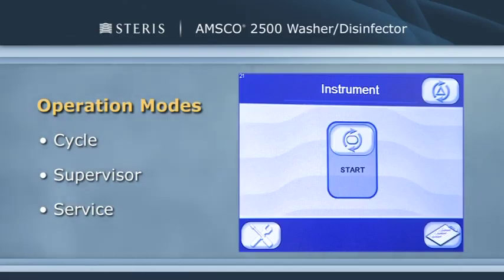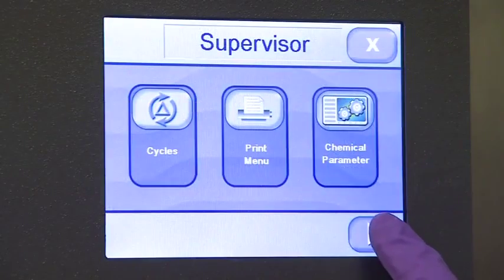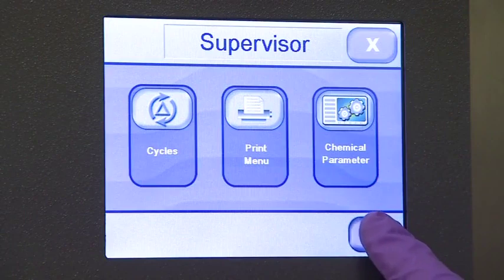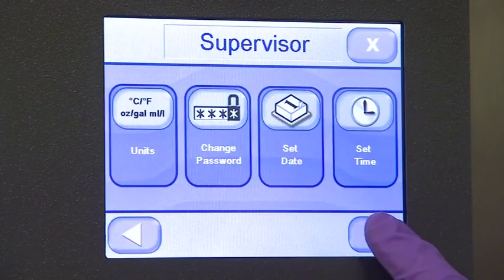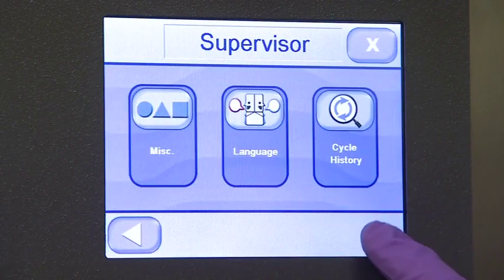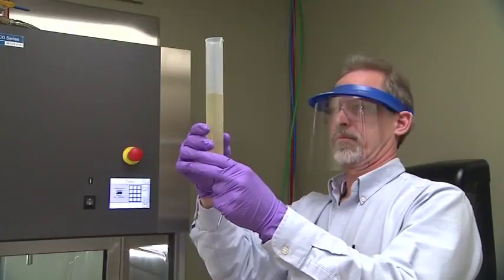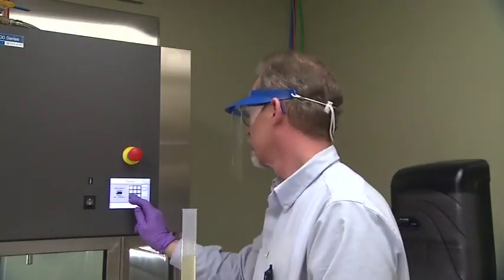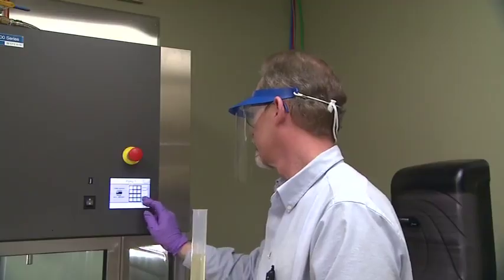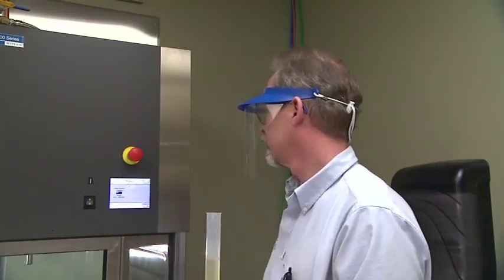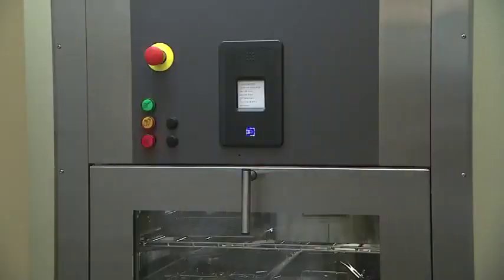There are 3 operation modes: the cycle mode, which is always available, plus the supervisor and service modes, which are password protected. Supervisor mode allows the modifying of pre-programmed settings, as well as date and time, enabling printer functions and setting operating language. Service mode allows a qualified service technician to access and configure the washer disinfector and perform preventive maintenance, testing, and troubleshooting. Next, note the series of status lights and confirmation buttons on the unit.